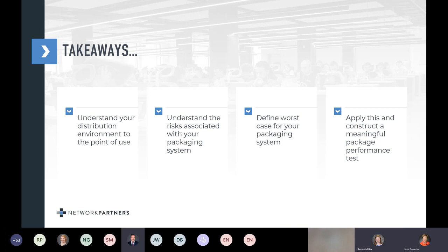Great, thank you, Jane. May I jump in? Sure. I just want to jump in with that question too. So just to build on what Jane said, the other reason I use 2x EtO is because there's really nothing that says worst case EtO sterilization, right? What I've seen in the past is you validate your sterilization cycle and you can get a half cycle. It could fault somehow. So if your validations or verification studies between the device and the package aren't qualified for 2x EtO, you're going to end up scrapping that entire product load in the sterilizer, which obviously is time and money, right?